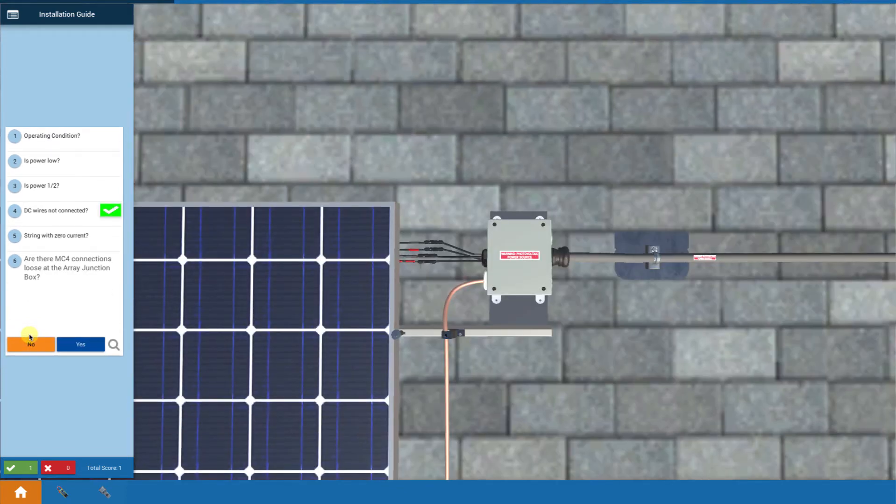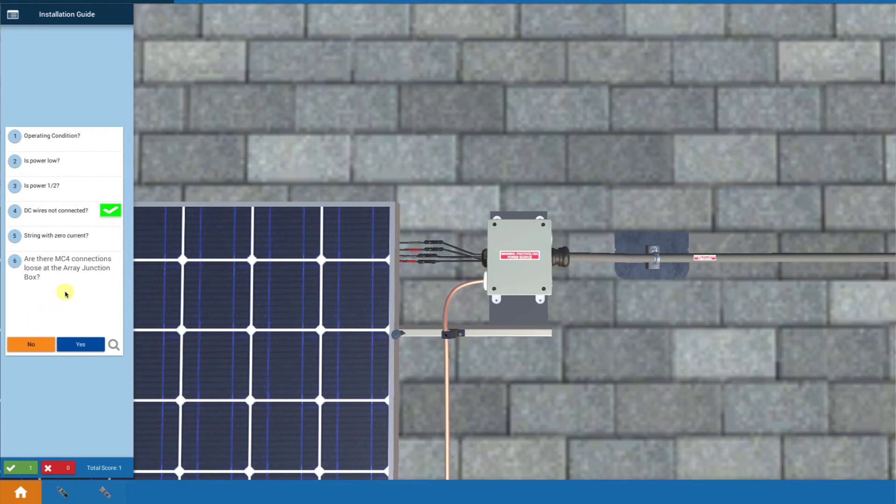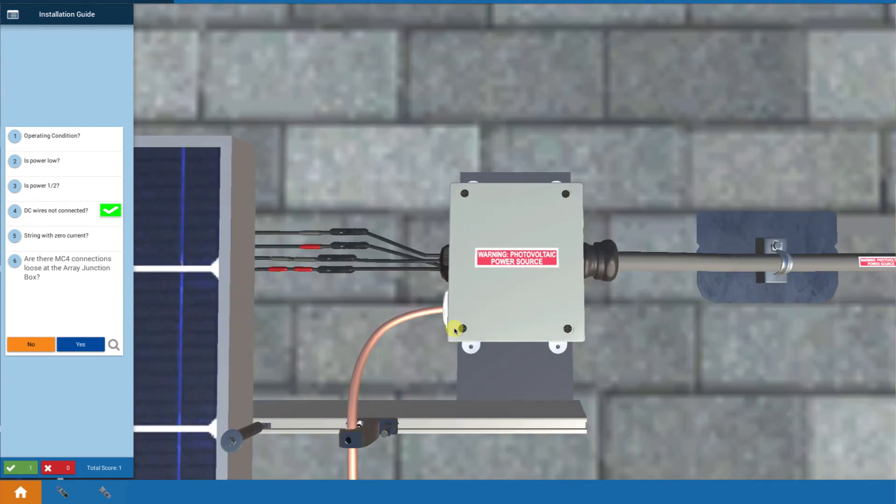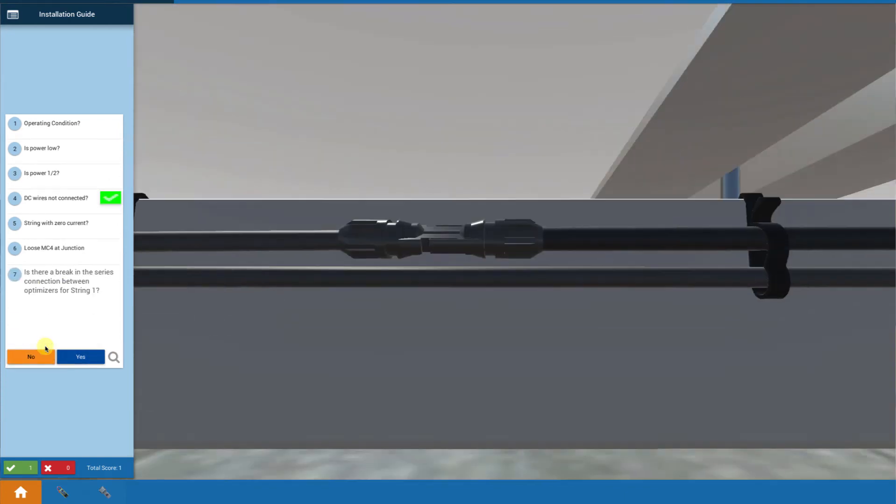Now I start looking at all the wires of my string one. Are there any MC4s disconnected up at the array junction box? If I zoom in, no, everything's good there. I've got my string one wires together, my string two wires together. That's okay, no problem there.